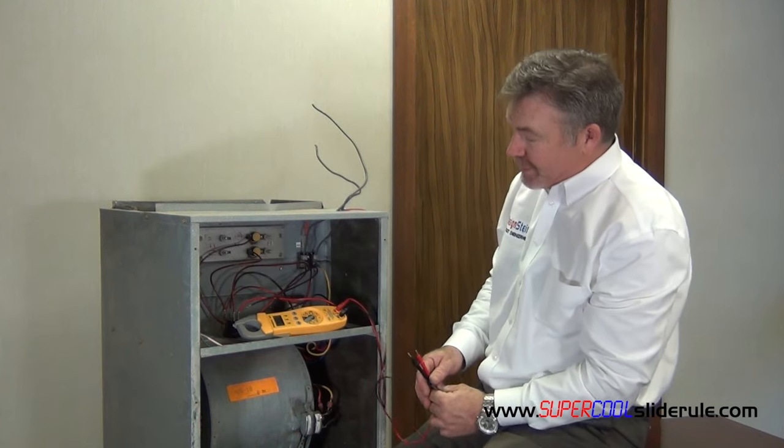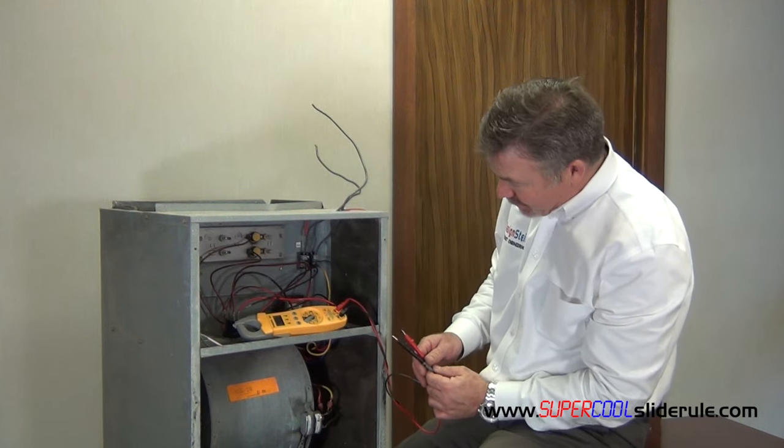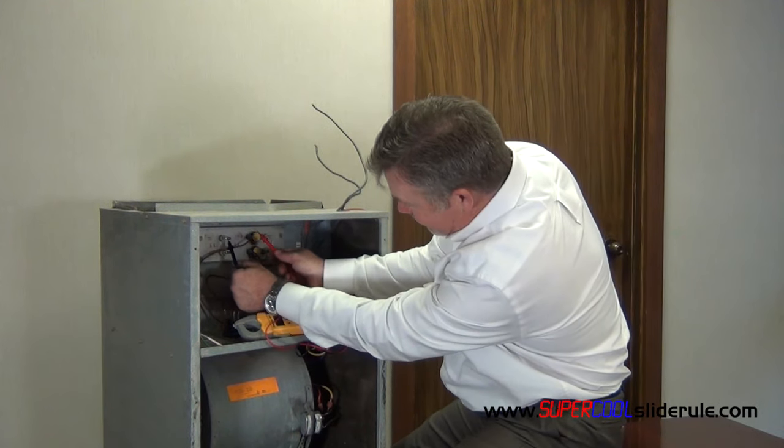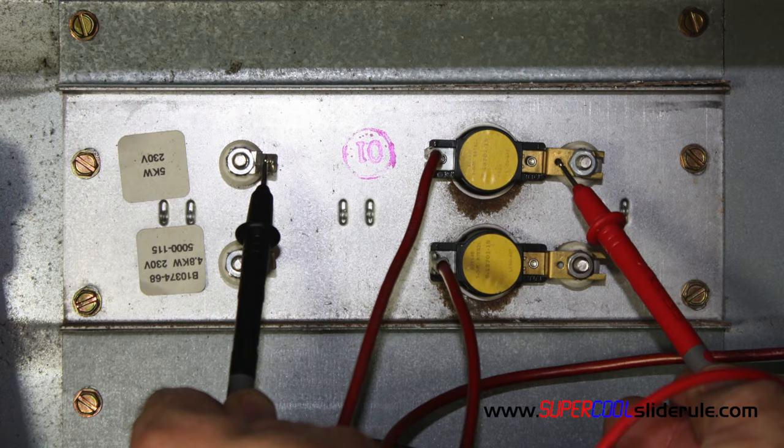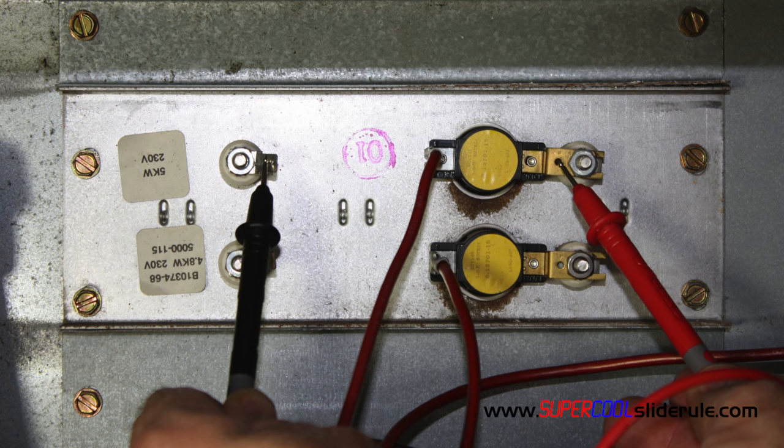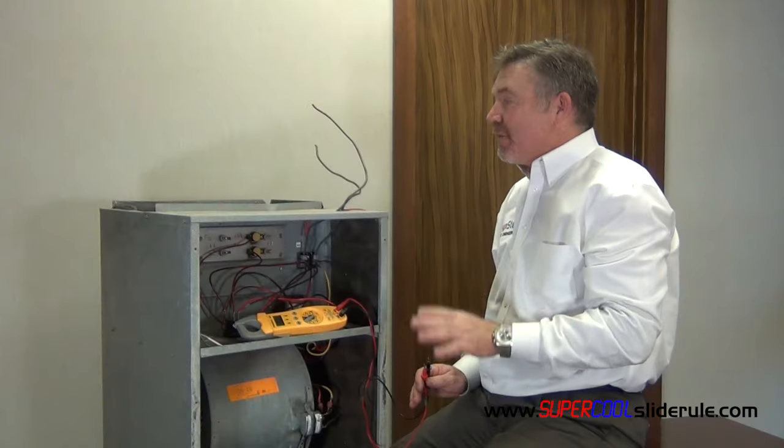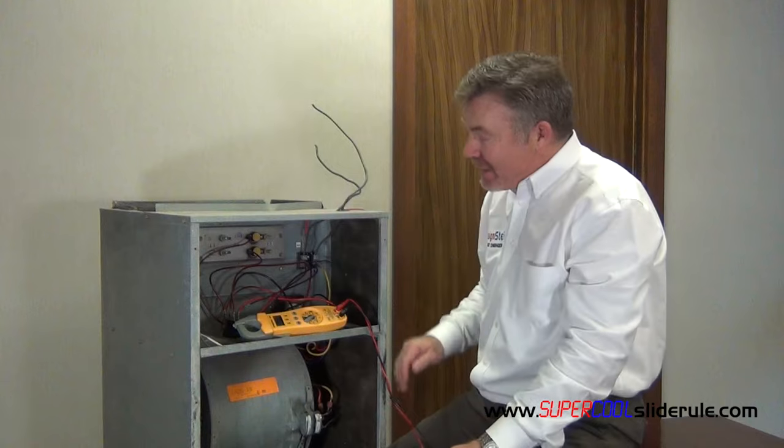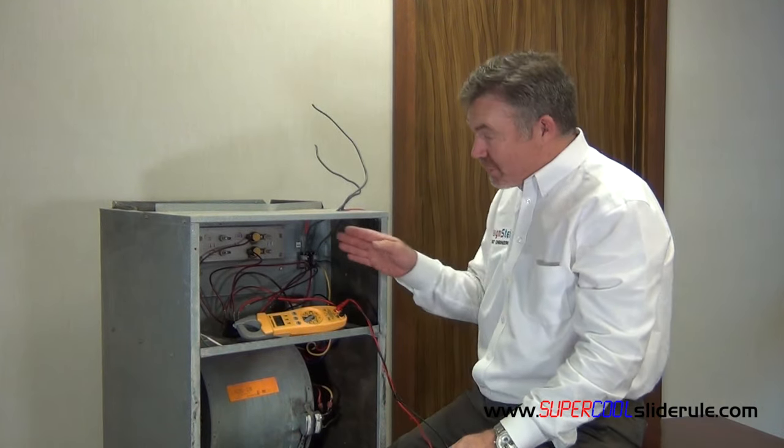So, if those were the readings, the next spot we would test would be, once again, all the way on the left side, and then right here where this bolt is on the right side, that will check the actual heating elements themselves. If we do have an OL condition, that will indicate that that heating element is burned out on that particular circuit.